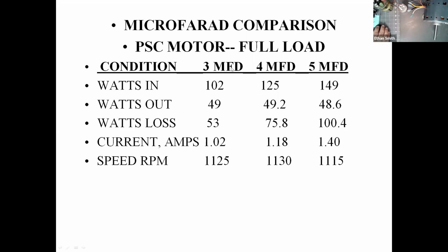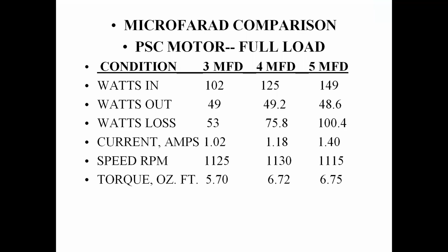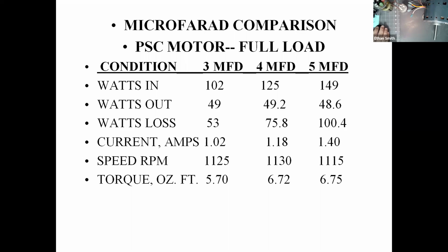And we can see that here, we're balancing running torque versus our efficiency. In this example where we had multiple different ones, we had a little lower overall torque with the 3 microfarad capacitor versus the 4 microfarad capacitor. But we do lose a little bit of efficiency when we go up to that 4, but torque was more important in this case, and so that's what we go with. And is that because it's adding sort of a third phase, right? A second phase, yeah. Okay.